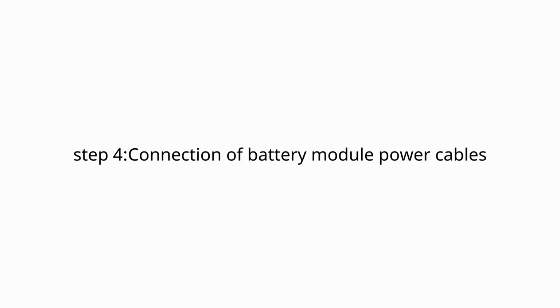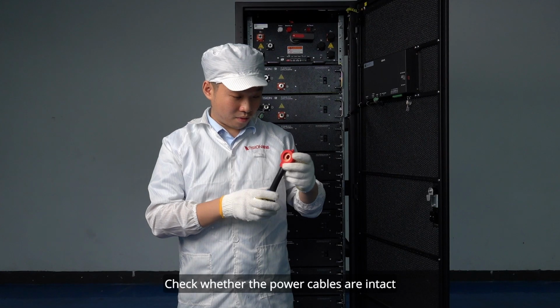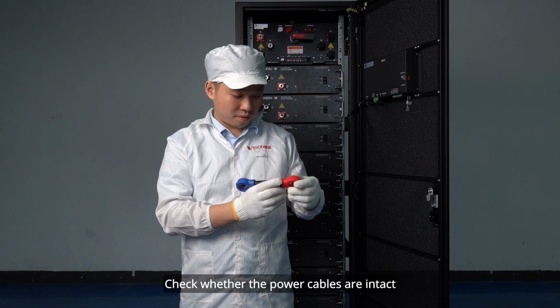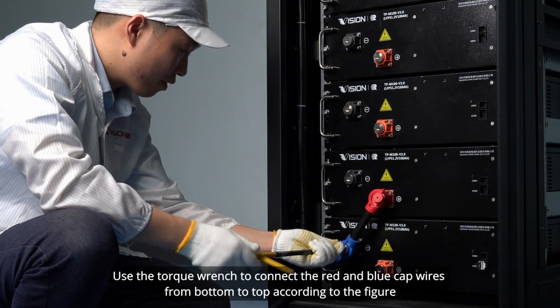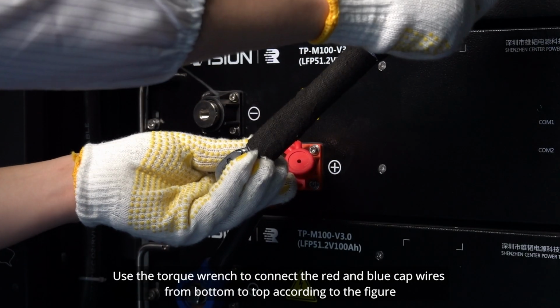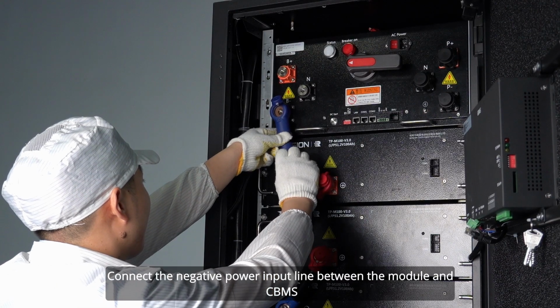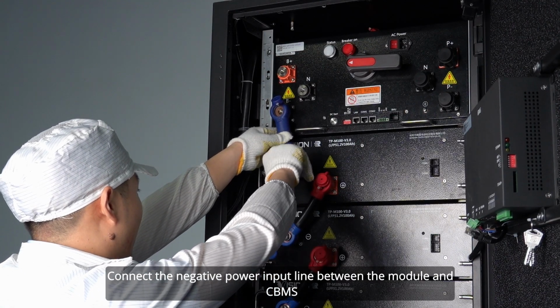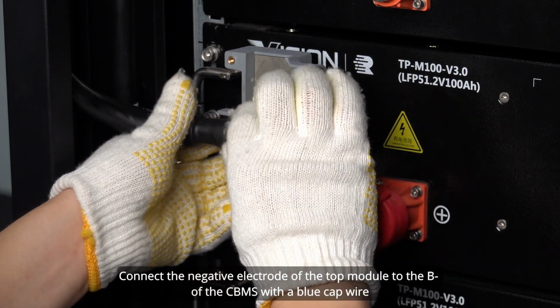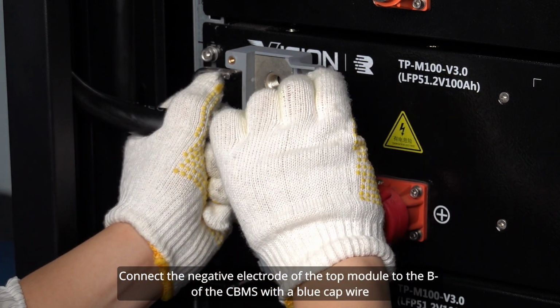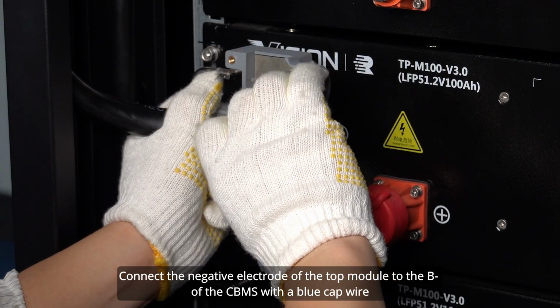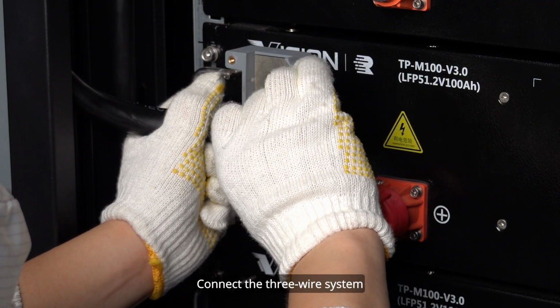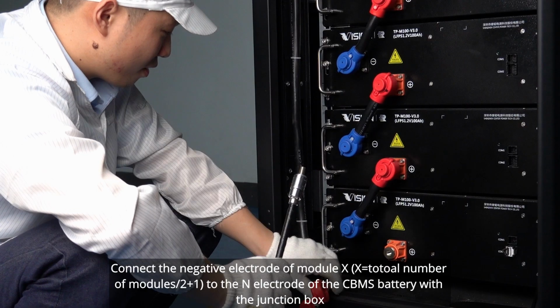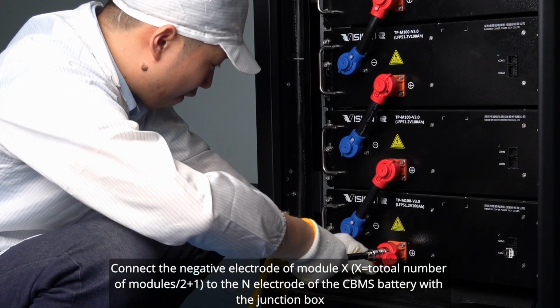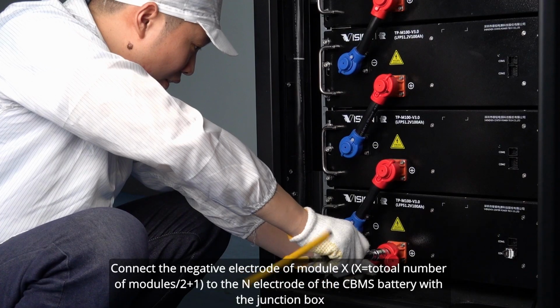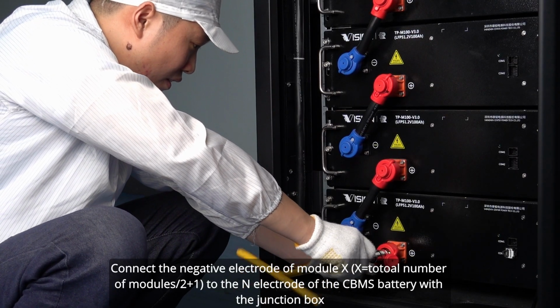Step 4. Connection of battery module power cables. Check whether the power cables are intact. Use the torque wrench to connect the red and blue cap wires from bottom to top according to the figure. Connect the negative power input line between the module and CBMS. Connect the negative electrode of the top module to the B- of the CBMS with a blue cap wire. Connect the 3-wire system. Connect the negative electrode of module X, where X equals total number of modules /2 plus 1, to the N electrode of the CBMS battery with the junction box.